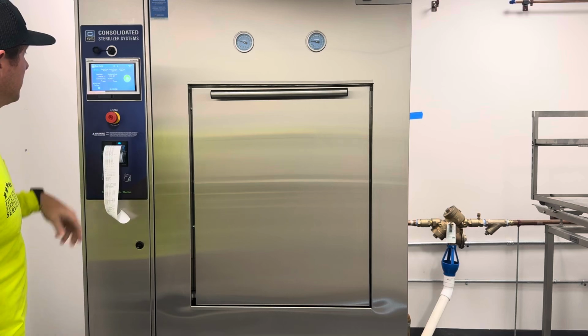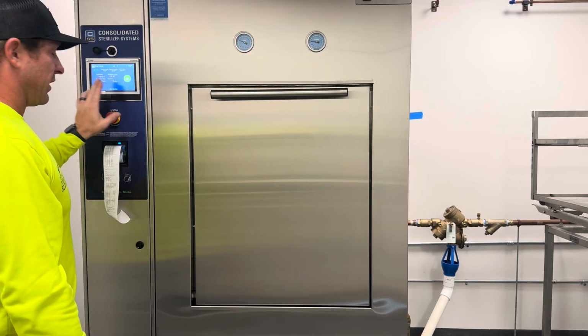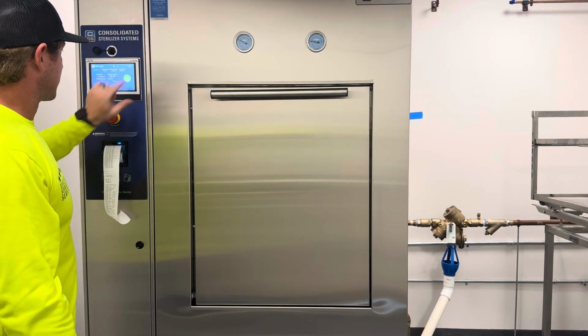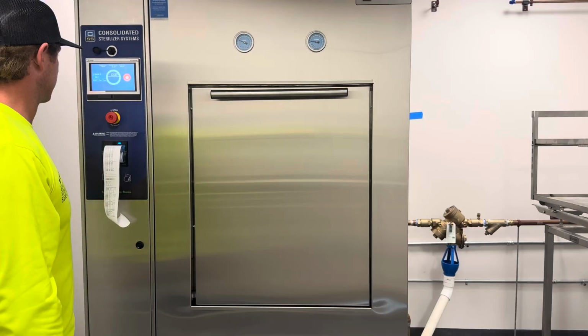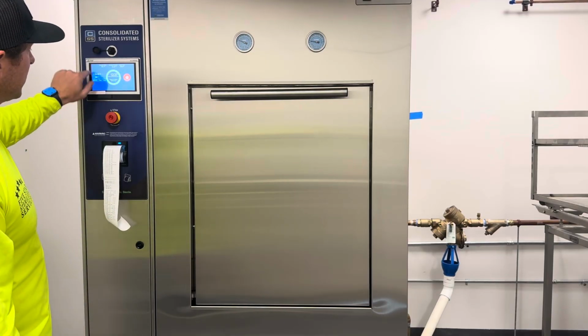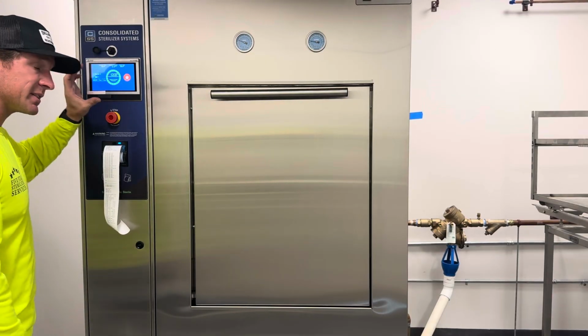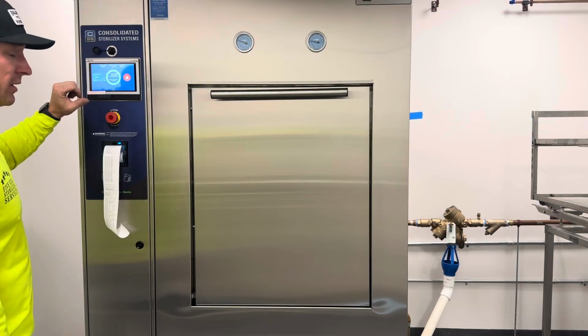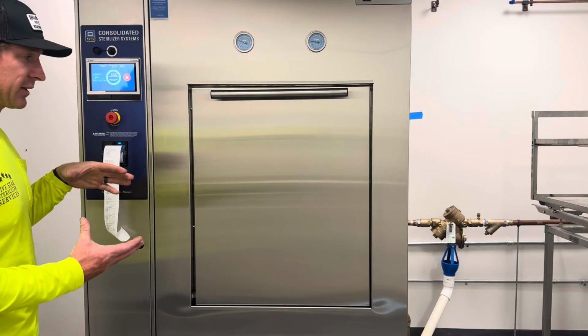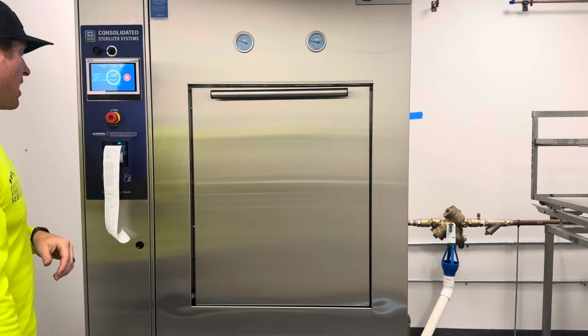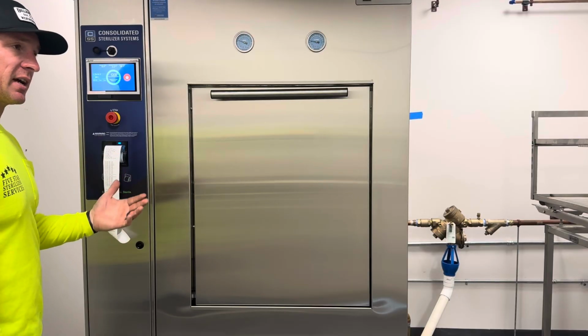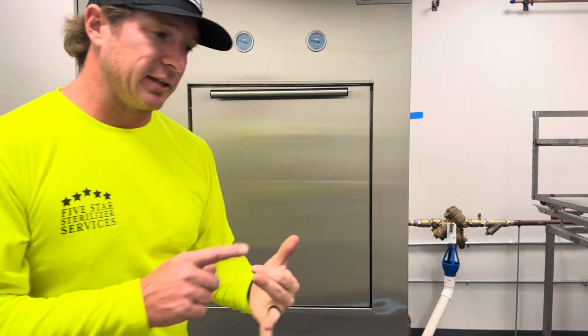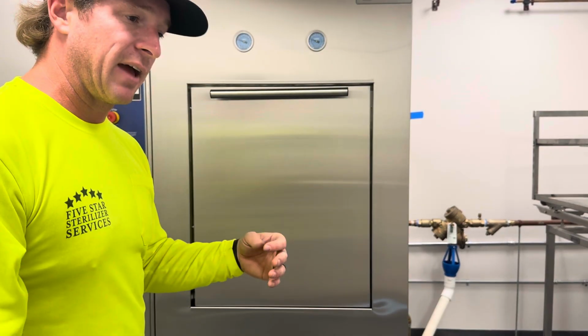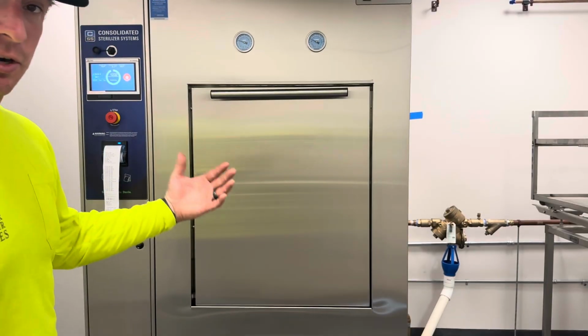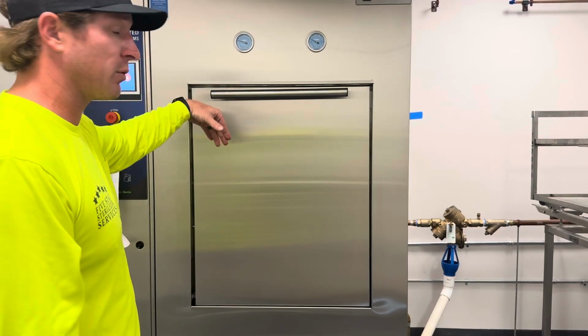Once my door is closed, I've verified my parameters. I'm gonna hit this green button, press to start. Okay, this is going to give me an estimated countdown for total cycle length, not the phase that it's on. So every cycle that you run, whether it's a gravity, liquid, or vacuum, all have phases. They all start with conditioning, which is what we're doing right now.